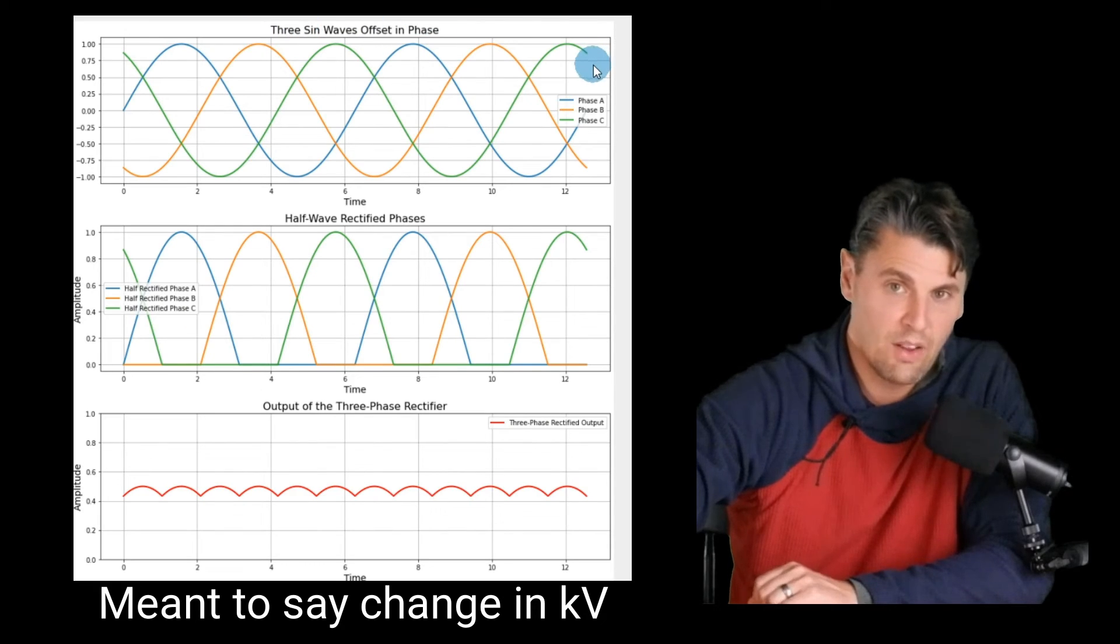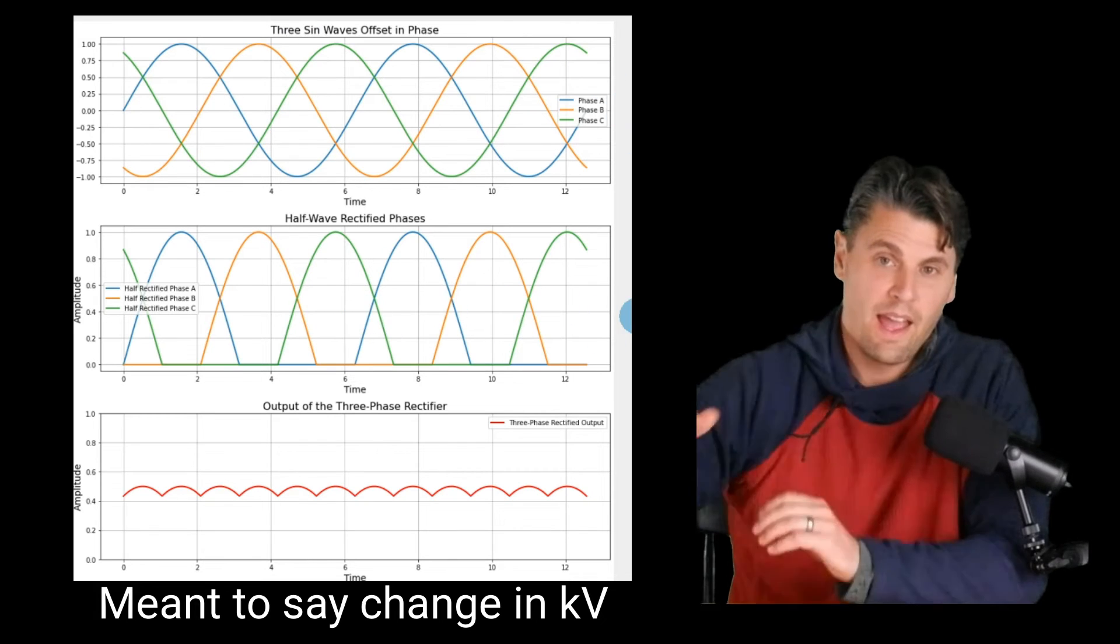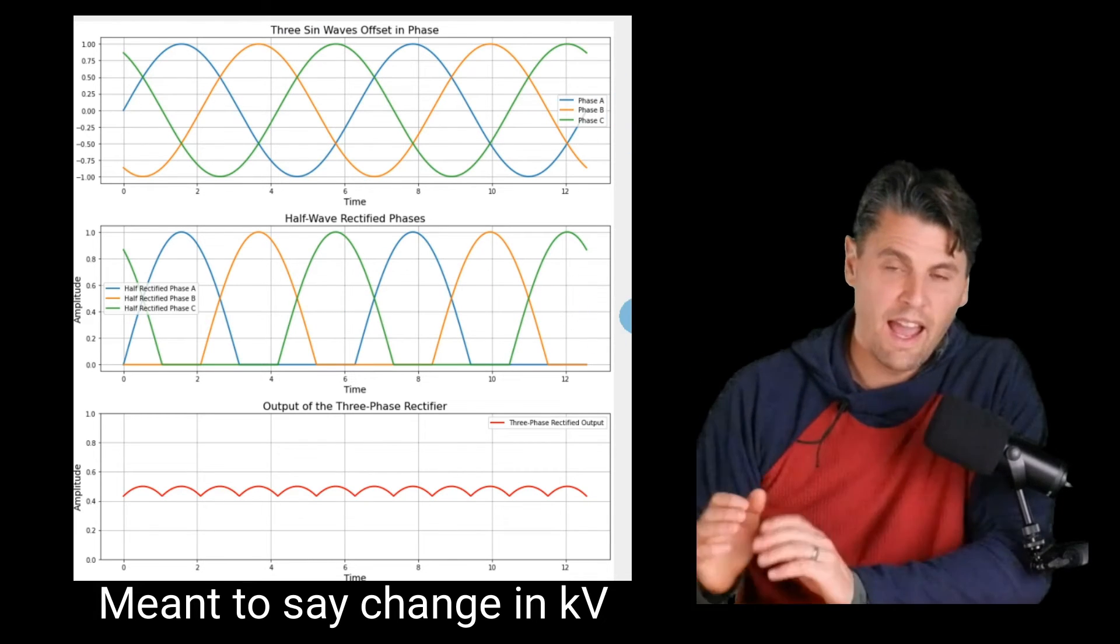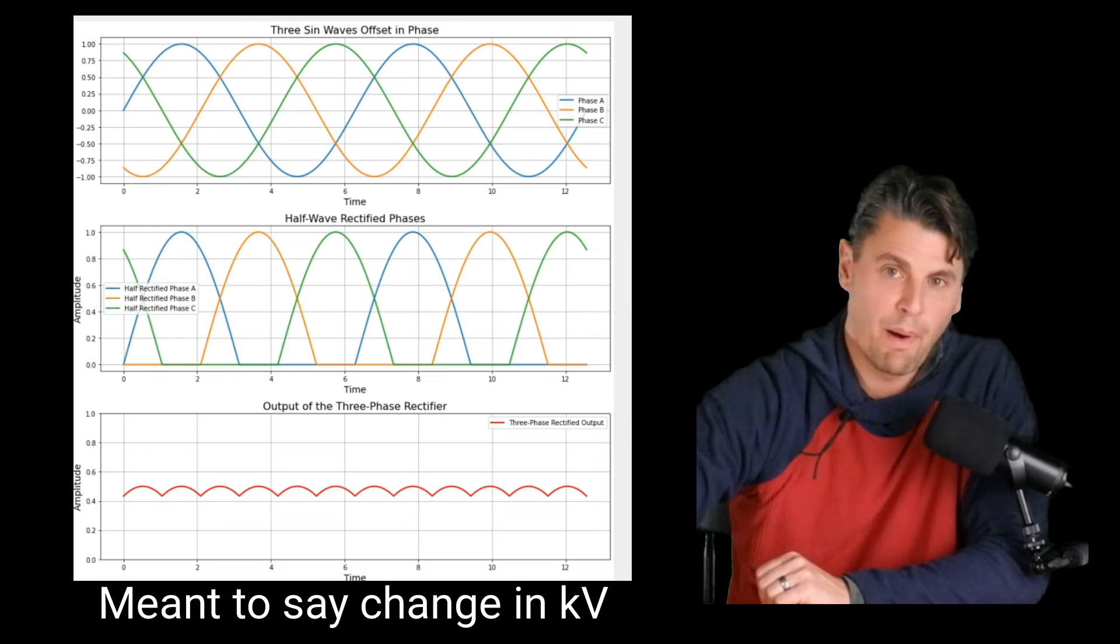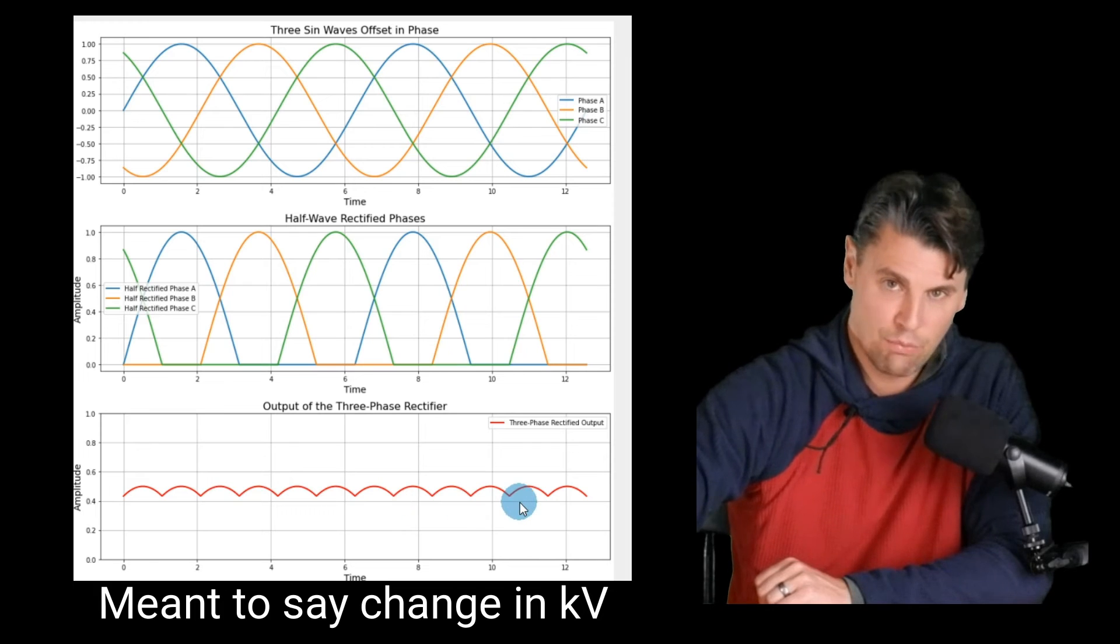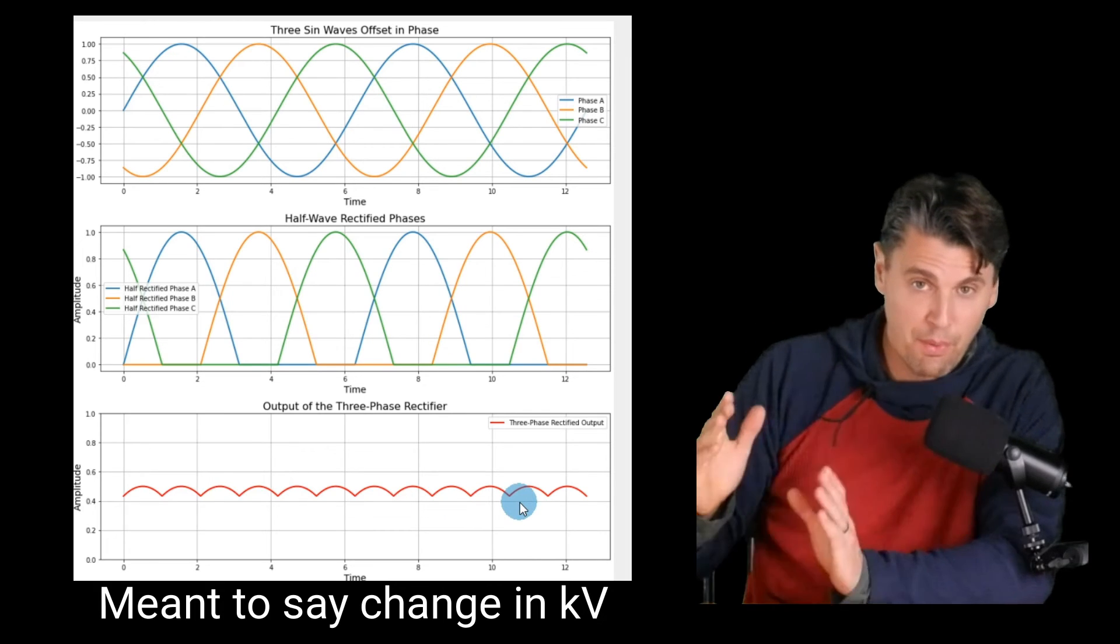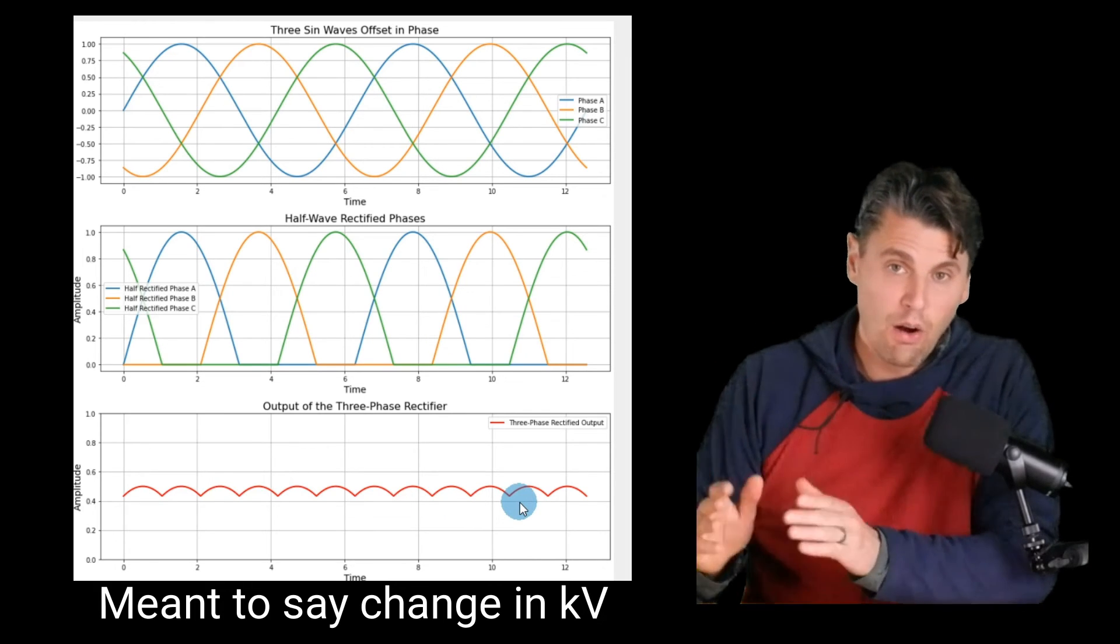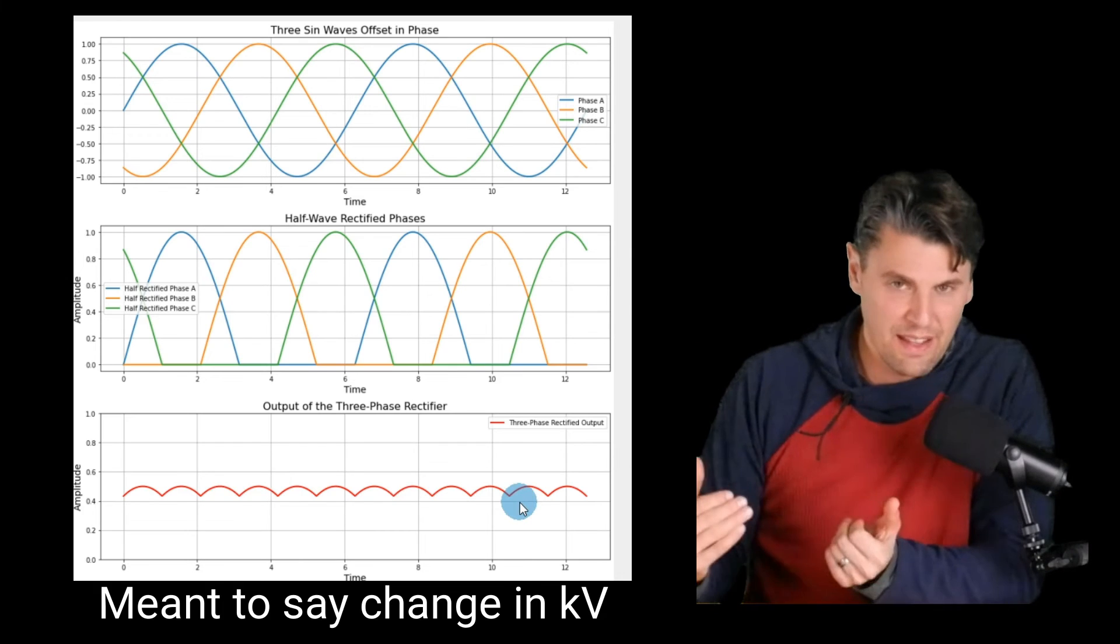Take that signal in and then we put it through half wave rectifiers. And then we actually combine those together, we can get a signal that looks like this. So if you see this signal now, coming out of what we call the three phase input, now there's significantly less ripple, and you can still see a little bit of ripple or change in kV over time, but it's significantly reduced.